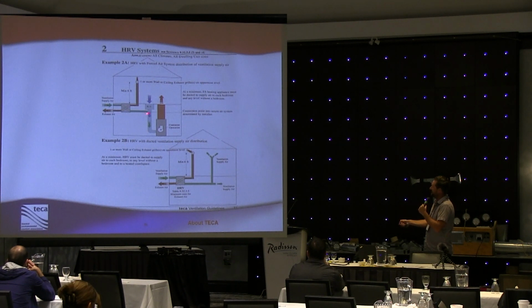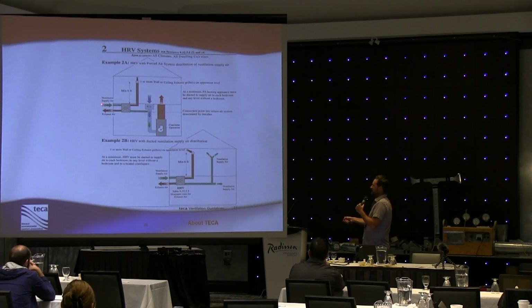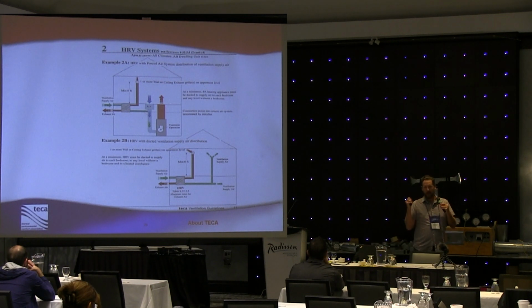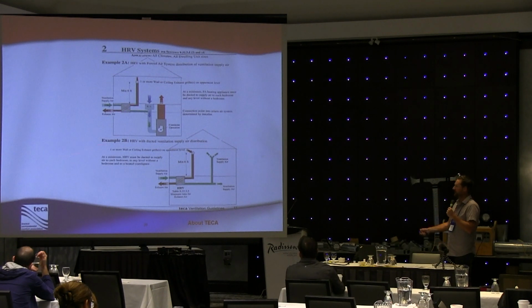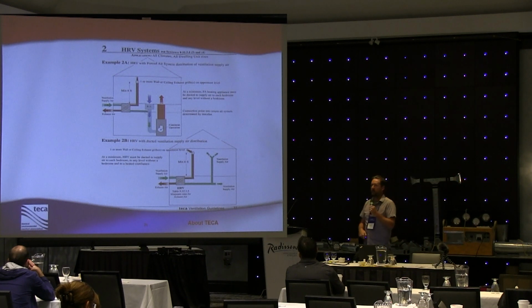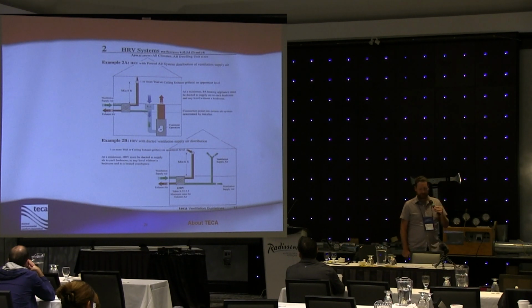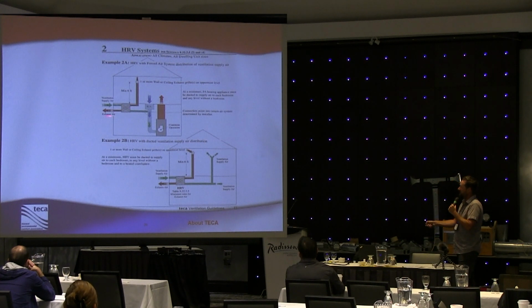However, rather than just having a passive ductwork that's bringing in fresh air from outside, we've got the HRV that's actually doing the function of bringing in the fresh air. That HRV is going to bring in fresh air from outside, and it goes through a heat exchange process where that cooler outdoor air can be tempered or warmed up with the stale air that we're exhausting. Like I said, there's a lot of heat energy stored in that, and as that heat energy transfers through the HRV's heat exchanger, it is going to strip away some of that heat and bring it into our fresh air coming in. So it is good for saving a little bit on the loss from the exhaust, the lost heat or the lost energy, if you will.